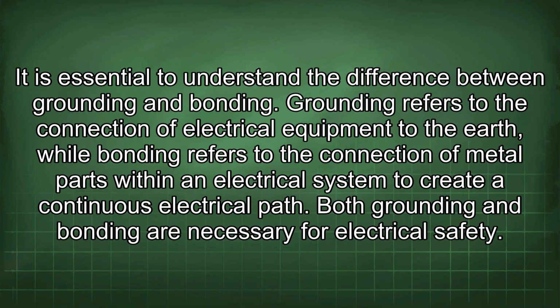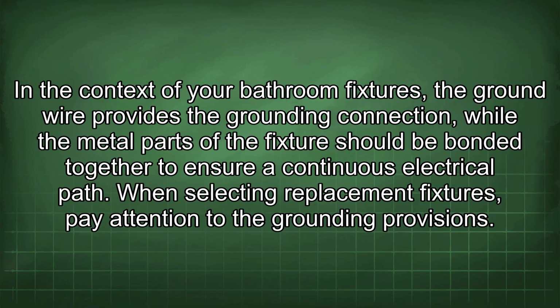Grounding refers to the connection of electrical equipment to the earth, while bonding refers to the connection of metal parts within an electrical system to create a continuous electrical path. Both grounding and bonding are necessary for electrical safety. In the context of your bathroom fixtures, the ground wire provides the grounding connection, while the metal parts of the fixture should be bonded together to ensure a continuous electrical path.